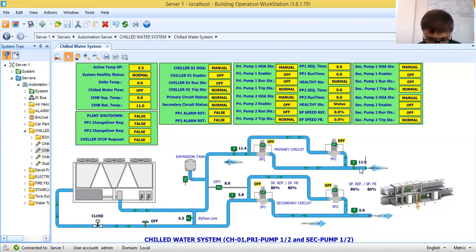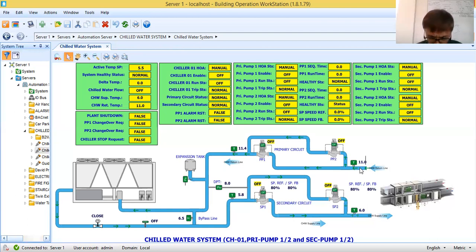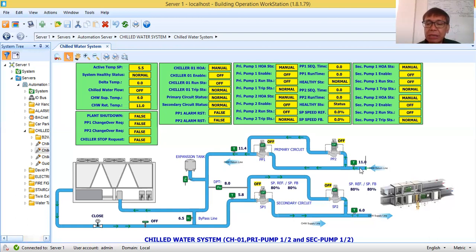The issue to prevent here is a loss of chilled water flow in the chiller when we are changing over the primary pump. What we can do is start pump two first, then when it is running, stop the working pump — let's say primary pump one. This way we will not lose chilled water flow in the chiller.